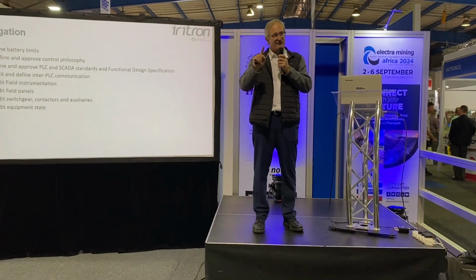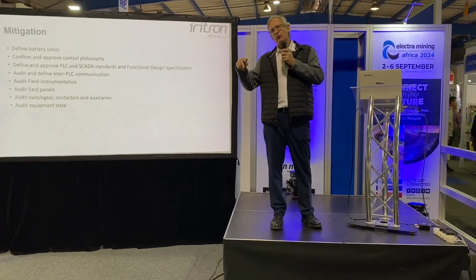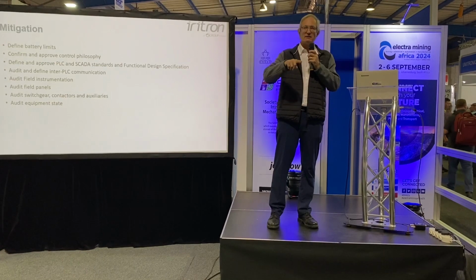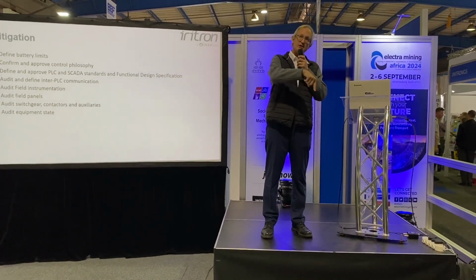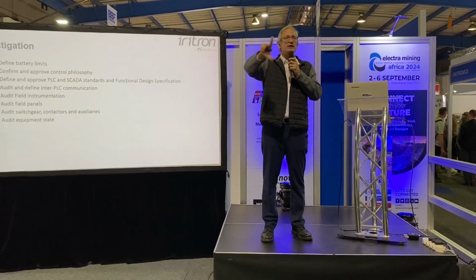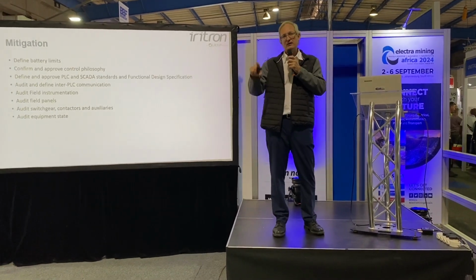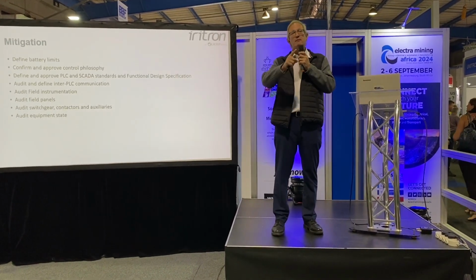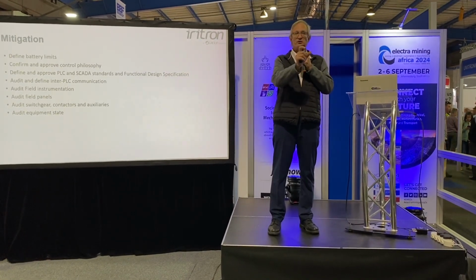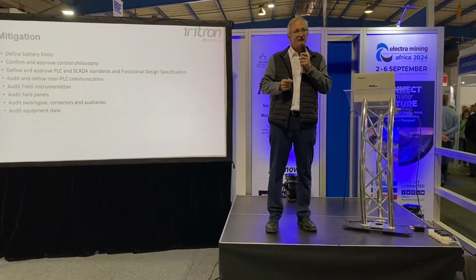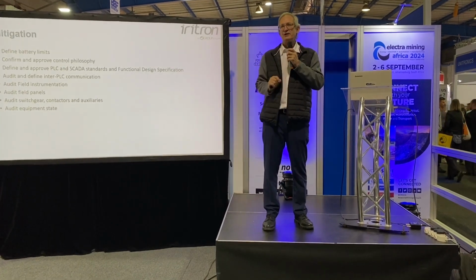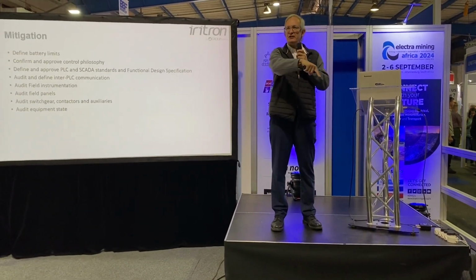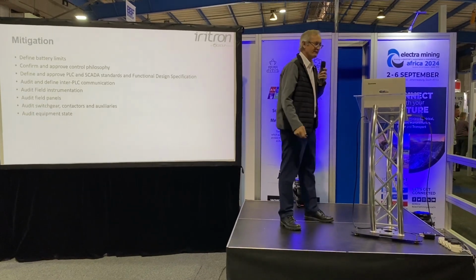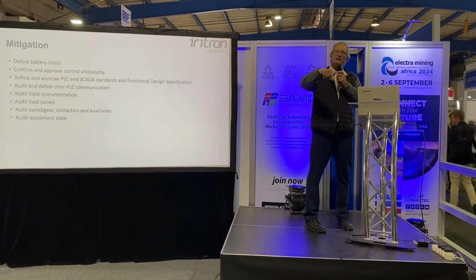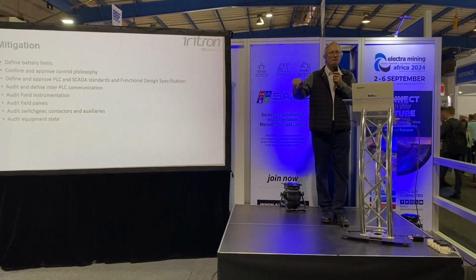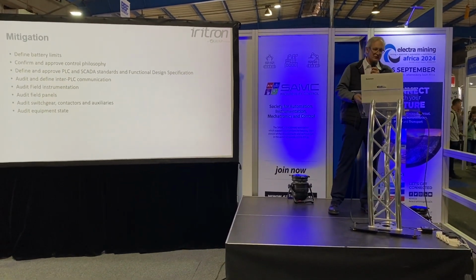They all worked. And then we actually went back and we looked at 2 years ago, we did a site visit and we took a picture of the SCADA system. And last year we went back and took a picture of the SCADA system. And in both instances, those amps did not show on the SCADA. However, we had to fix it. They went, put in CTs, and we had to make it work. It became our problem because we did not identify that before we started the project and before we started commissioning on site.